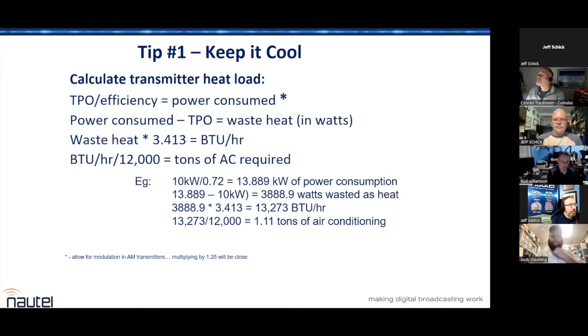So yeah, waste heat's the big one. All you need to know is your TPO, your output power, and your efficiency. The rest is pretty basic. Once you've got that figured out, calculating waste heat in either BTU per hour or tons of air conditioning is pretty easy. Remember, when you calculate this number, all you are looking at is the waste heat from that piece of equipment.